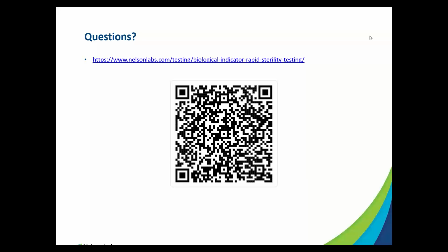How would justifying this new incubation method apply to the European community for CE marking a product line? That's a great question, and it's really going to go back to your notified body and the change control. So it is going to require a change assessment form with your notified body, and a lot of the documentation will still stand as is. The notified body may ask for a little bit more, and that's what Nina kind of indicated. We're preparing some of that. Right now, we've rolled out in the US, but the intent is to roll out in Europe, and with that, we will be working on putting together somewhat of a package that the notified body can use or you can provide to the notified body.